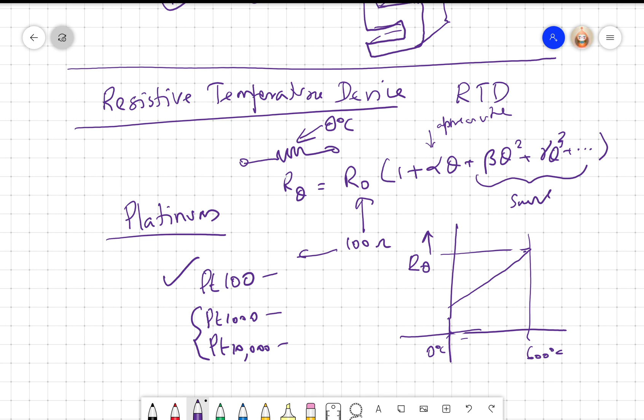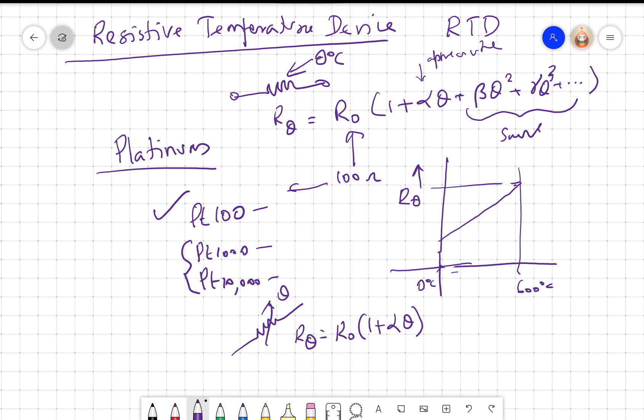So RTD is a temperature sensor. I have the resistance varying with respect to temperature, where R theta equals R naught, where R naught is the resistance at 0 degree centigrade, times 1 plus alpha theta, where alpha is the temperature coefficient.